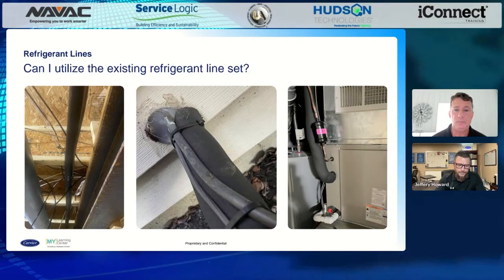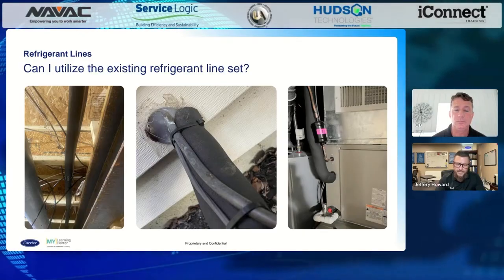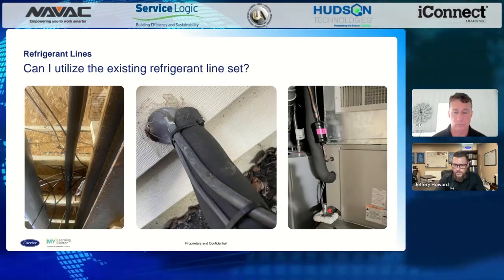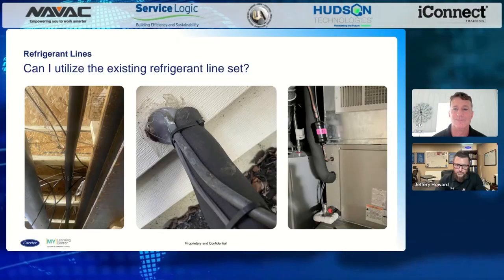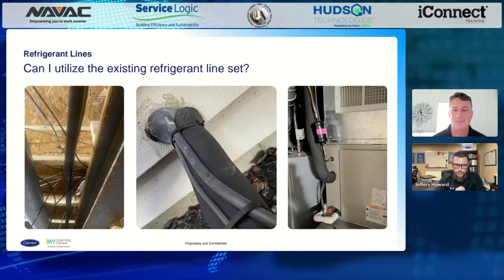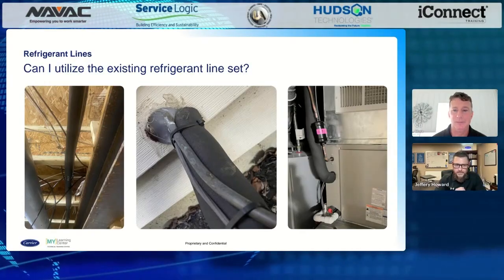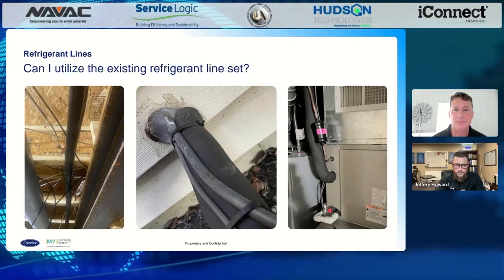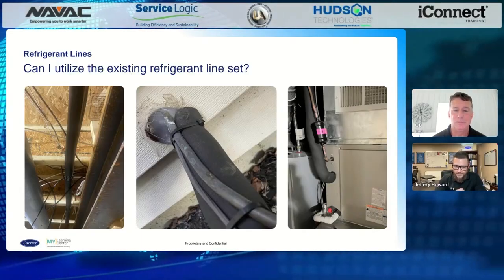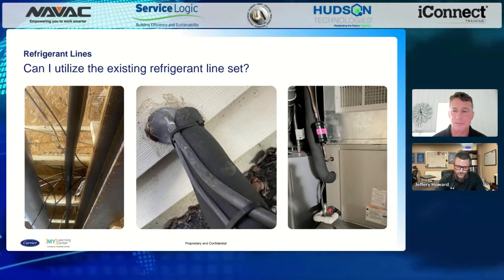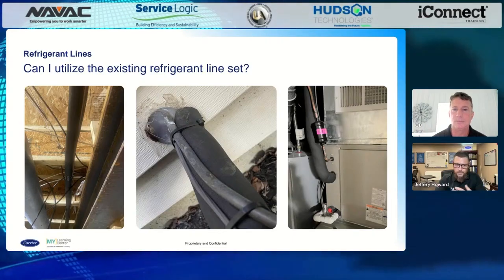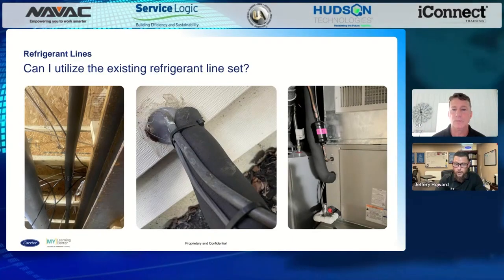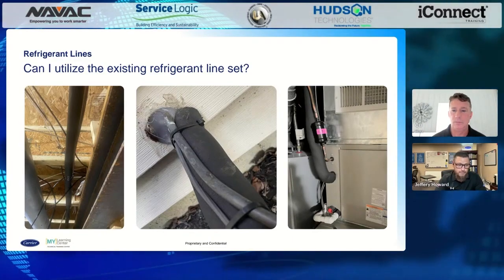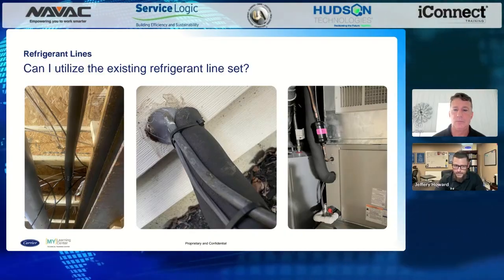Also, as long as you dehydrate or clean out the line, purge the lines, clean the lines, and of course we'll talk about evacuation and things like that too. That's very, very important. So yes, you can reuse the existing line set, as long as there's no kinks, tears, or breaks anywhere inside those lines, and we maintain them, take care of them, and clean them.